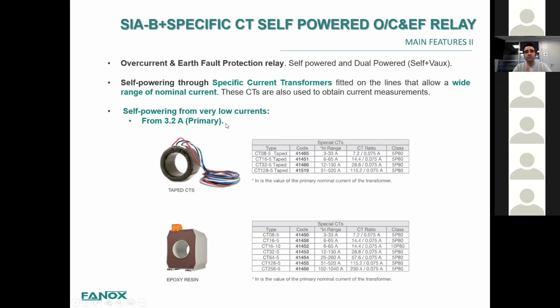It's important to remark that the relays have a self-power value from very, very low currents. So as you can see here, from 3.2 amps, our relay will have enough energy to be awake and to trip if necessary.